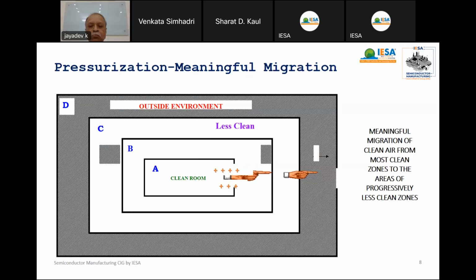What is the meaning of pressurization? Suppose you want to make a room clean. The first principle is to keep the room at a positive pressure compared to the surroundings, so that ingress of contamination from outside into the room will be prevented. So you can see a picture here. Indirectly you can call it a meaningful migration of clean air from the cleanest zones to the areas of progressively less clean zones. For example, clean room A is the cleanest room. From that, air goes to the next, slightly diluted room, and then into the outside atmosphere as a corridor. That's why, if we keep a pressure gradient, we can avoid the ingress of contamination.